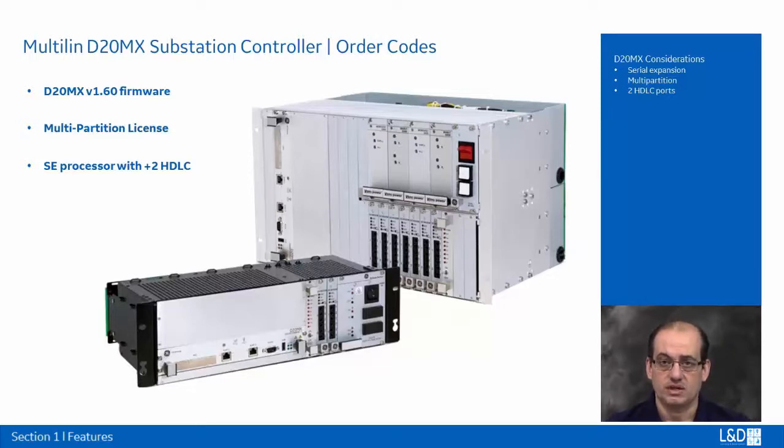One of the great features that is allowed is multi-partition, and this is a decision that would have to be made whether we should make the applications live in different virtual environments from a software perspective, or all of the applications will be on the main board. If you need that capability, like let's say you have multiple logic that have to run in one environment and another logic that has to run in another environment, then that's available in multi-partition, and you would have to order a multi-partition license for it.